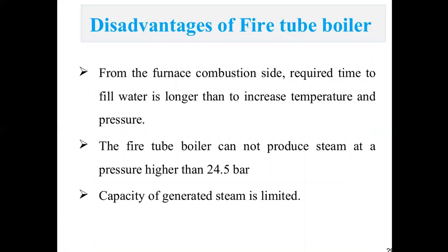Now the disadvantages of the fire tube boiler. Compared to the furnace combustion side, it requires a longer time to fill the water and to increase the temperature and pressure. These fire tube boilers contain a large amount of water, so if the water is more, it takes more time to increase its temperature and pressure. That means converting water into steam takes more time compared to the water tube boiler.